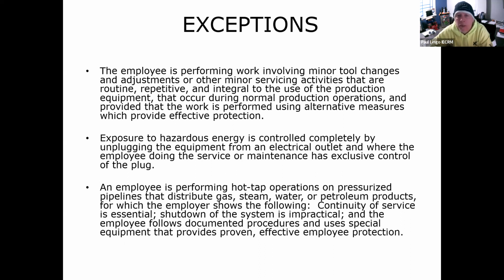Remember, if we're doing our safety checklist correctly, we should really only have to don that PPE one time when it comes to de-energizing a piece of equipment or locking it out. If we have selective coordination and labeling - and we've all gone to an electrical panel and opened it up and couldn't tell what a single circuit is, all the time, it's infamous in our industry - that's where this whole procedure starts: the identification of your energy, what it's doing, where it's going.